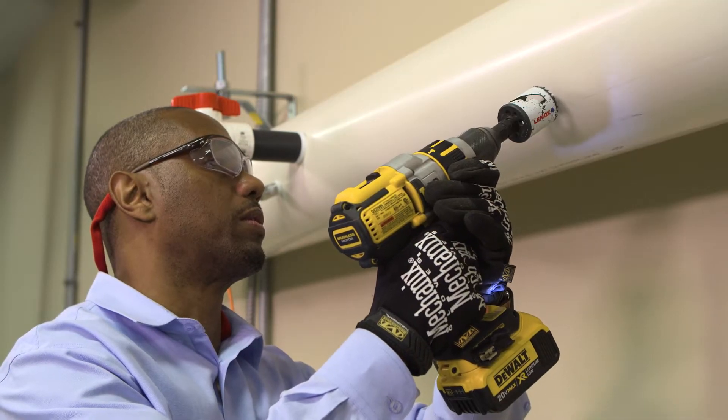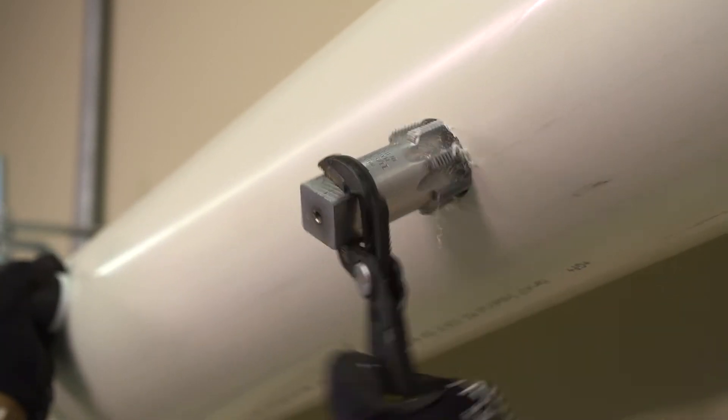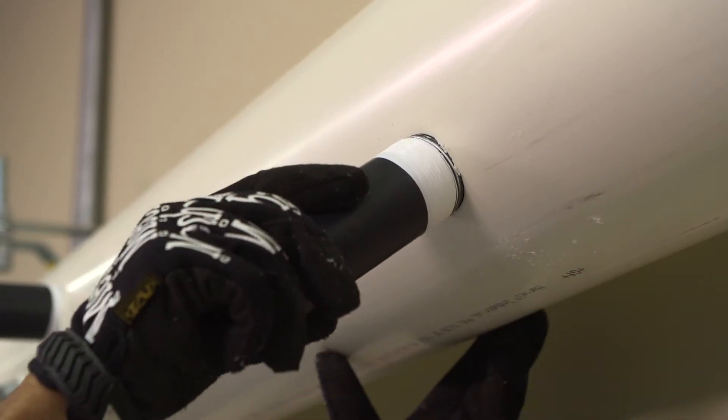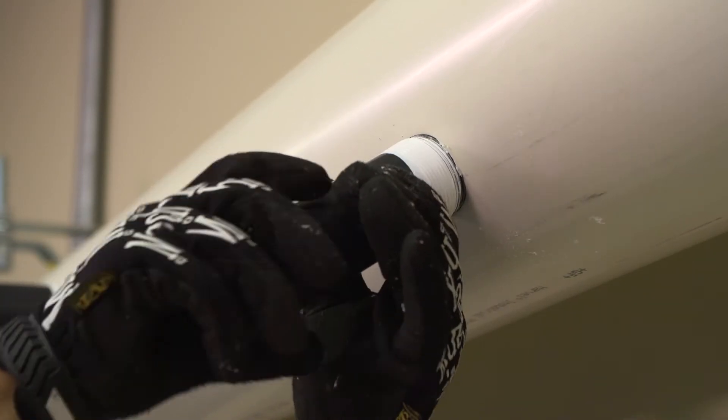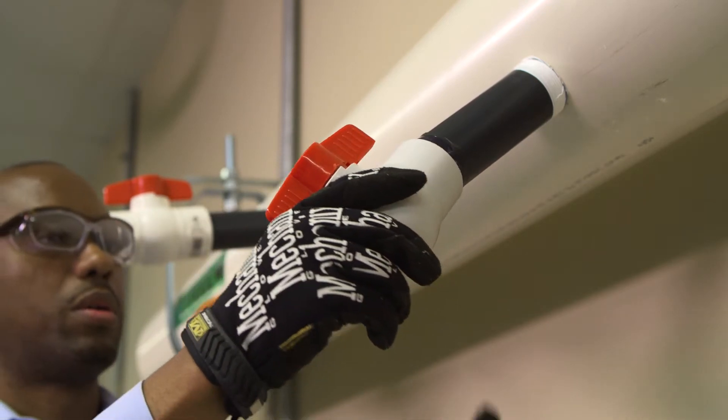Drill and tap a second 1.5-inch NPT hole downstream of the first. This hole accommodates the discharge side of the pump. If automated controllers are used in the system, the drilled and tapped hole must be placed downstream of the ORP and pH probes. This is to avoid problems that may occur with the controller operation. Thread the second nipple into the tapped hole or saddle clamp. Take another 1.5-inch ball valve and glue it onto the second nipple.